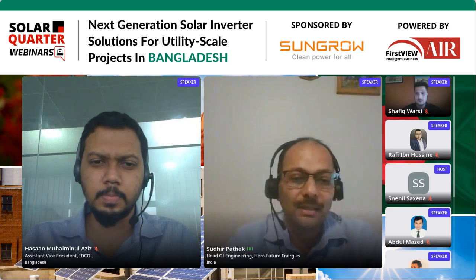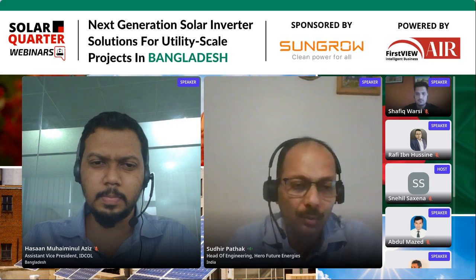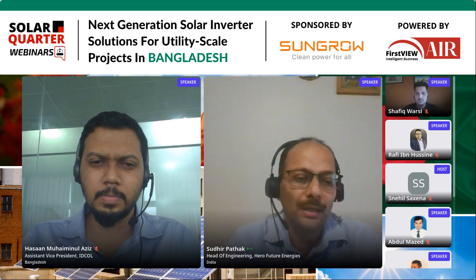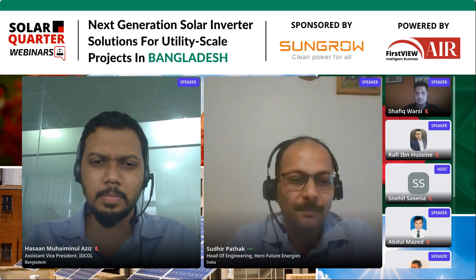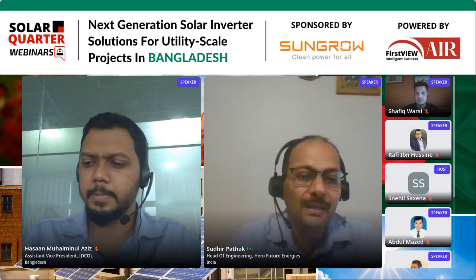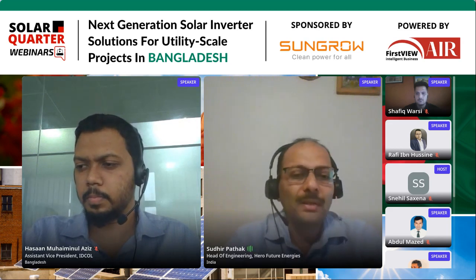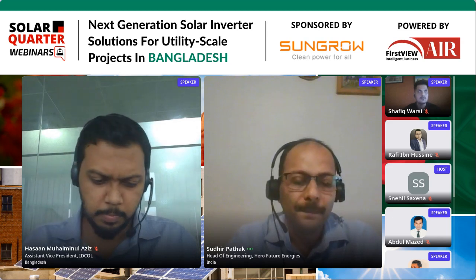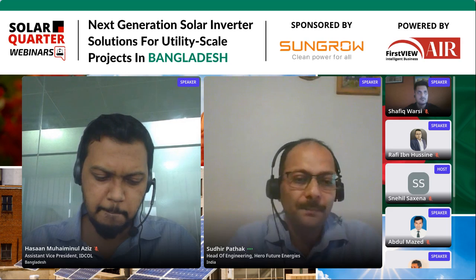Another advantage is that, as one of the speakers was saying, data is much more important now. Putting up a solar plant is an easy job. Running it for 25 years is, I think, a tougher job. And running at your projected yield, whatever you have estimated. If you are taking central inverters, you need to have string level monitoring. For string level monitoring, you need string monitoring boxes, right?